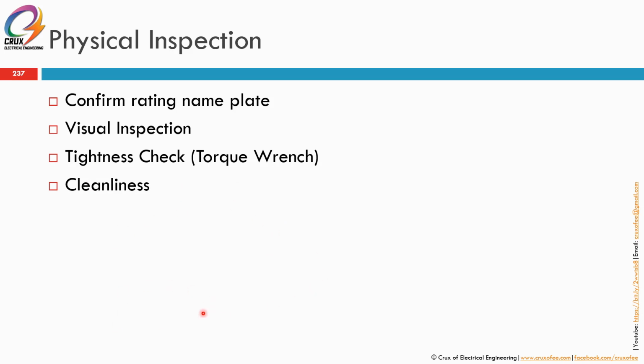Make sure that at the cable termination there's no crisscrossing for a 3-core cable, from one phase to another phase, to minimize any partial discharge activity in the long run. Make sure the earthing is correctly installed. If the earth braided wire should be going through the ZCT, core balance CT, things like that. These are the things that require physical inspection.